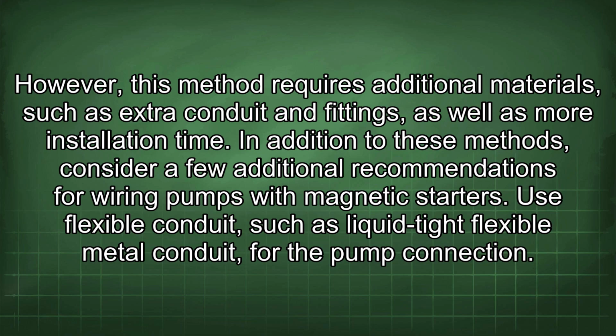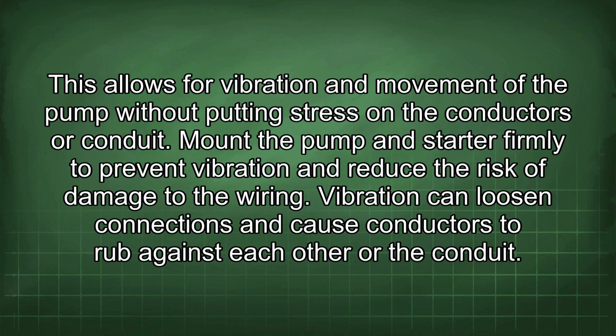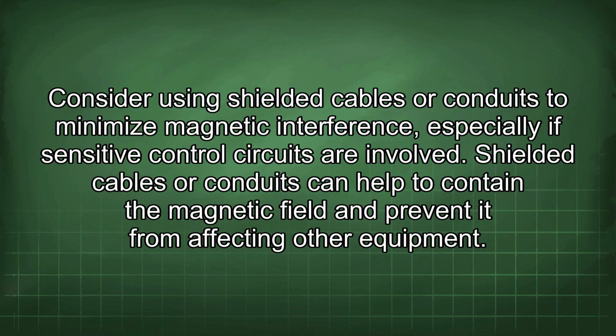Use flexible conduit, such as liquid-tight flexible metal conduit, for the pump connection. This allows for vibration and movement of the pump without putting stress on the conductors or conduit. Mount the pump and starter firmly to prevent vibration and reduce the risk of damage to the wiring. Vibration can loosen connections and cause conductors to rub against each other or the conduit. Consider using shielded cables or conduits to minimize magnetic interference, especially if sensitive control circuits are involved. Shielded cables or conduits can help to contain the magnetic field and prevent it from affecting other equipment.